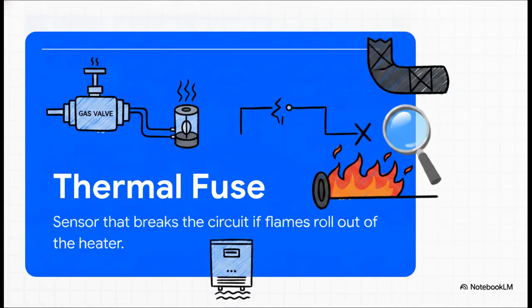Moving down the line, we have the thermal fuse, sometimes called a fusible link. This is a vital heat sensor right near the gas valve, and it contains a small wax pellet. If an exhaust blockage causes flames to literally roll out the front of the heater, that wax melts and permanently breaks the circuit. It's essentially a suicide switch. Unlike other sensors, it can't be reset. It must be completely replaced, but honestly, more importantly, you have to clear that dangerous blockage before ever firing it up again.